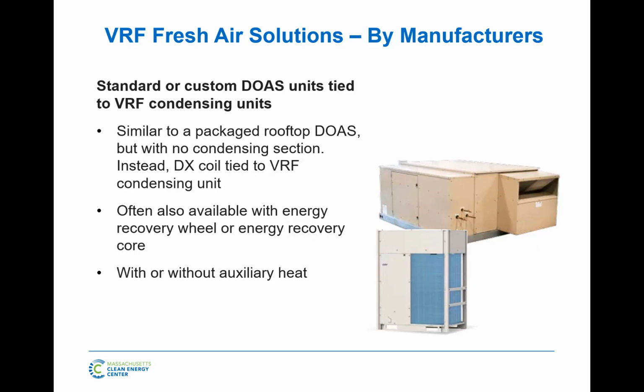The DOAS systems are very popular. This is a picture of, to the naked eye, it looks like one of the rooftops you see on the roofs everywhere. It's not a regular rooftop. It is meant for fresh air, whether it's 100% fresh air or partly. So a couple of things have happened here. You can buy a regular DOAS unit by any manufacturer and throw that onto your building, and that handles the fresh air, and it's completely independent from whatever VRF you're putting in the building.